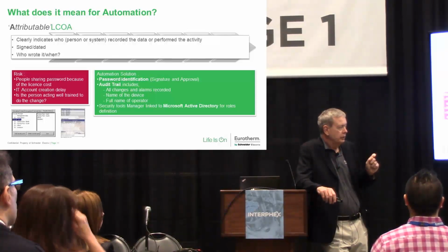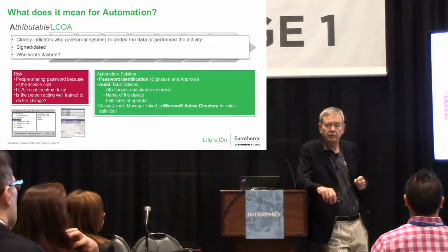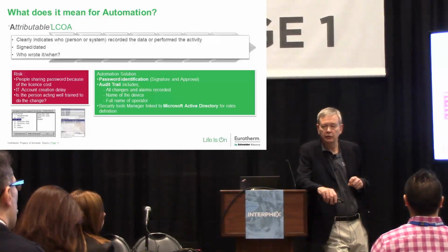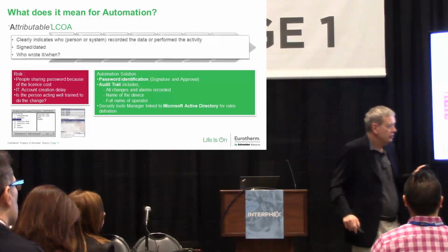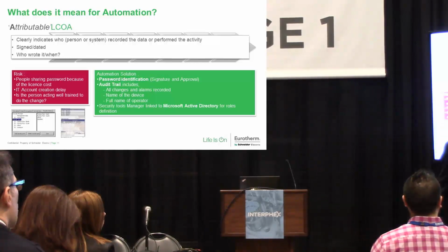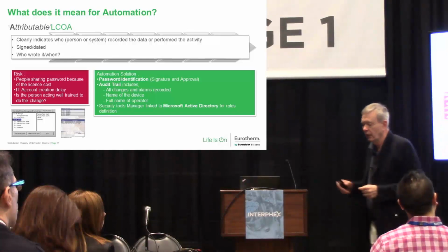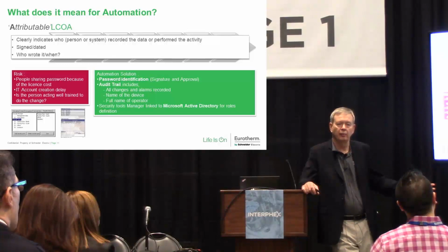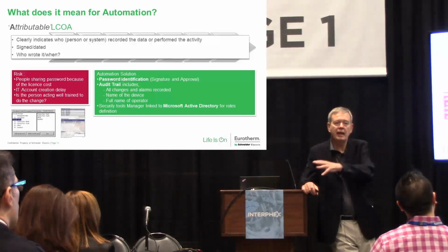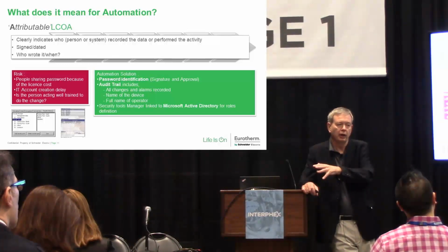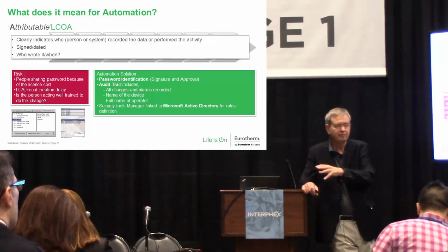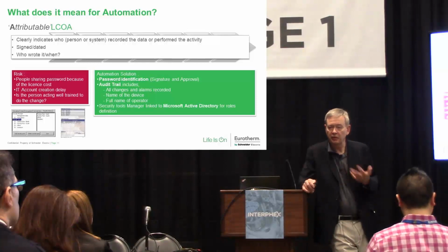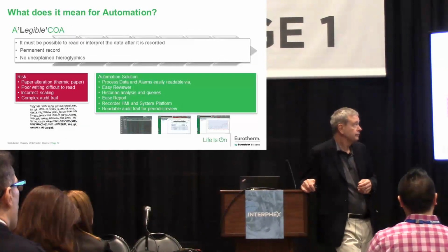Another great way to review a new automation system to make sure that it's passing your 4.0 requirements and your data integrity requirements is to make sure that the password system you put in place can take advantage of Microsoft Active Directory. That simply means that the passwords associated with the system can be managed back on the network through Microsoft Active Directory. Not all automation systems out there that you might be thinking about have that capability.